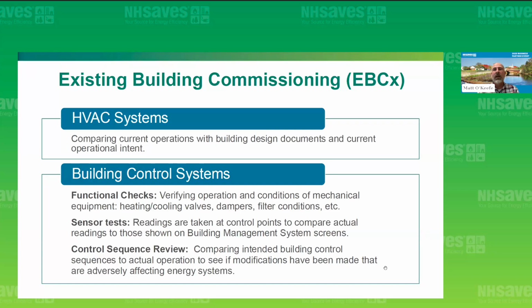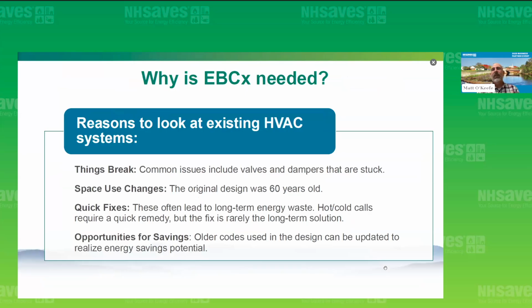So, the initial design of an HVAC system, who knows how long ago it was when it was initially developed, but I bet a lot has changed and they might be using it differently than it was initially intended, sometimes for better, sometimes for worse. So why is it needed? Even though equipment might be found to be broken or stuck in a fixed position, it still might not alert facility staff if the downstream point of measurement, like room temperature, is still being met. Nobody's calling to complain, so it could be going on for a very long time, likely overusing heating and cooling sources to do so.